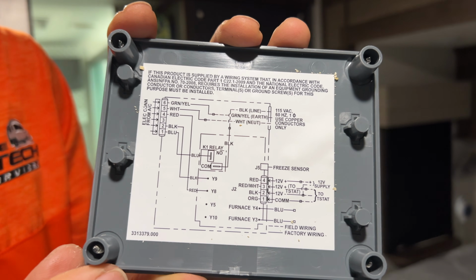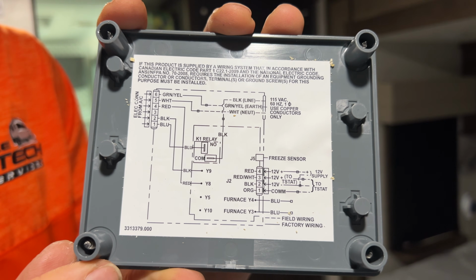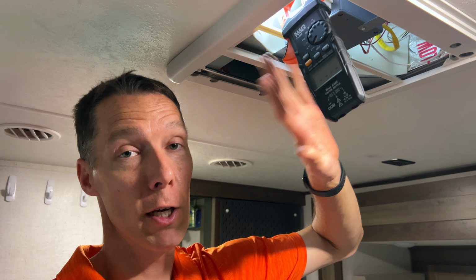And we're on the blue wire for this Dometic AC unit. It sometimes can be a black wire or a purple wire. You have to follow the wiring diagram to know for sure based on which unit you're working on. You can also check it right here out of the control box, or by pulling the cover off the AC unit on the roof and checking the wire into the air conditioner compressor.